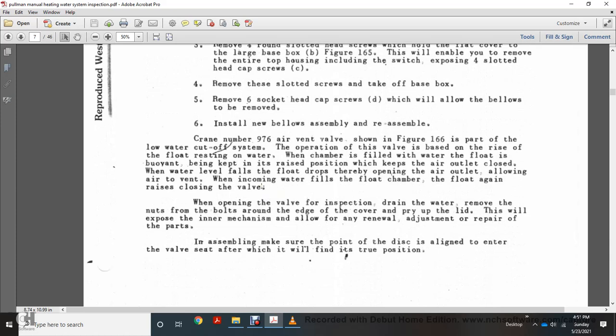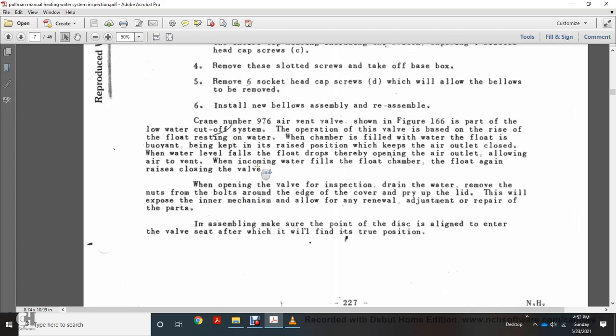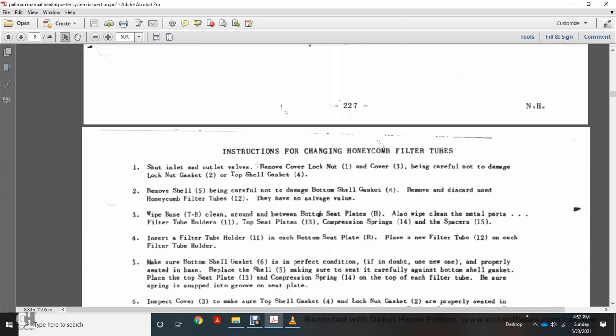The air vent valve, shown in figure 166, is part of the low water cutoff system. The valve operates as follows: with the float resting on the water in the float chamber and the chamber filled with water, the buoyant float is kept raised, keeping the air outlet closed. When the water level drops, the air outlet opens, allowing air to vent. As incoming water refills the float chamber, the float rises and closes the valve. For inspection and drain: remove the nuts from the bolts around the edge of the cover, pry up the lid — this will expose the inner mechanism of the valve. When reassembling, make sure the point of the disc aligns with the edge of the valve seat, after which it will find its true position.